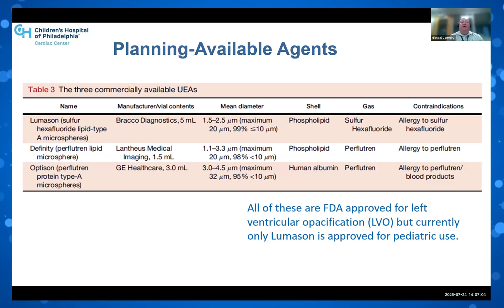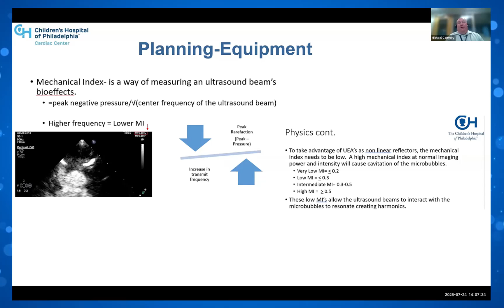I don't want to make this a physics talk, but this is important, and I'll get to that in a second, of pediatric transducers for cardiology are very specific for what we need to do. In theory, with any type of ultrasound, the higher the frequency you're going to use, the better you're going to resolve, and you want to use as high a frequency as you can. To avoid bubble cavitation, we're going to lower the MI. And I'm saying that because we want to use the highest frequencies we can.